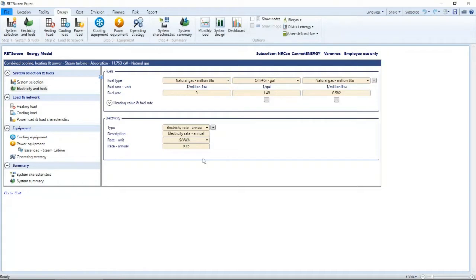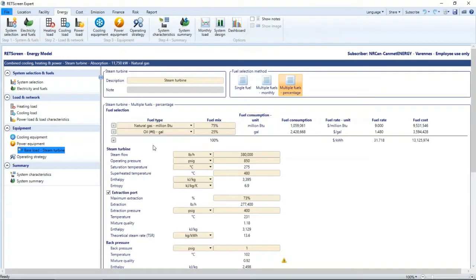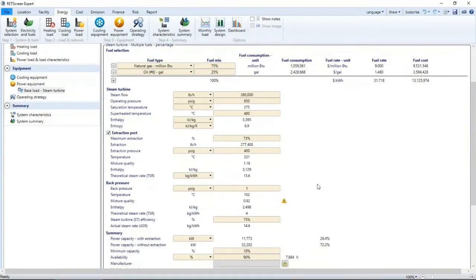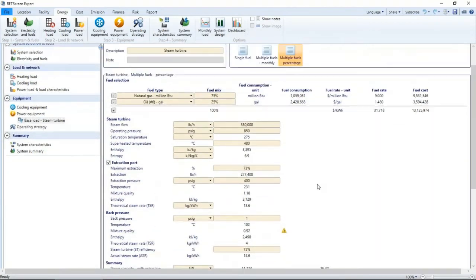From the steam turbine form, I could understand that the system uses 2 high-pressure steam boilers to feed the steam turbine. One boiler is oil-fired and the other one uses natural gas. 75% of the year, the natural gas boiler is utilized. To include 2 fuels, the multiple fuel option was selected.